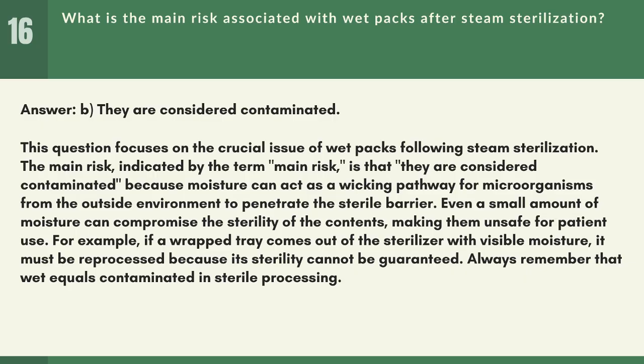Even a small amount of moisture can compromise the sterility of the contents, making them unsafe for patient use. For example, if a wrapped tray comes out of the sterilizer with visible moisture, it must be reprocessed because its sterility cannot be guaranteed. Always remember that wet equals contaminated in sterile processing.